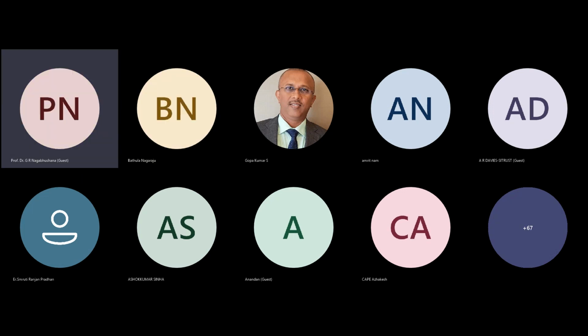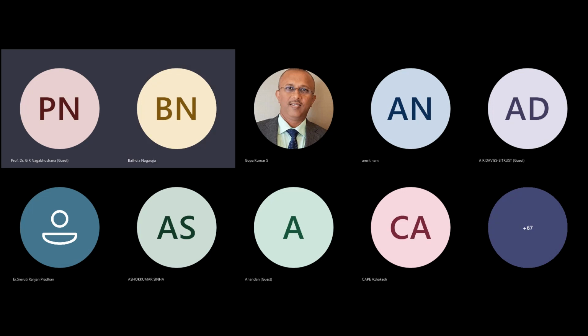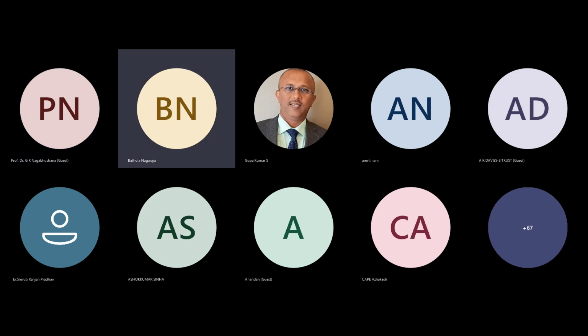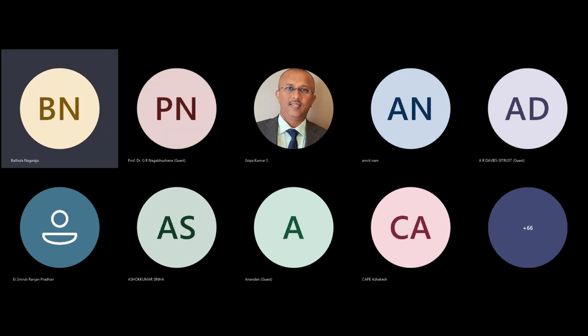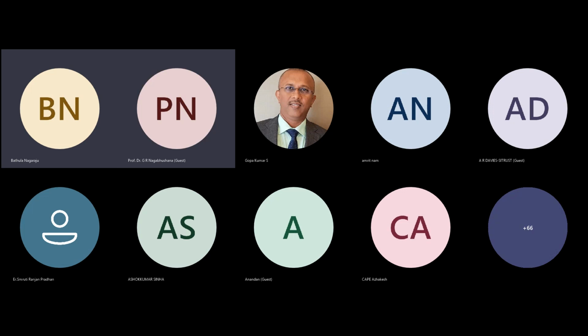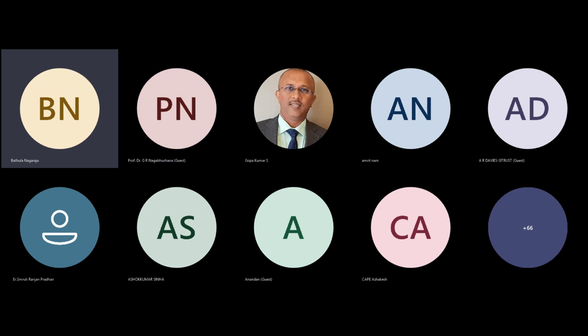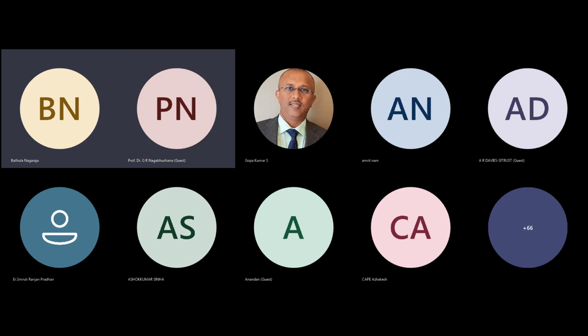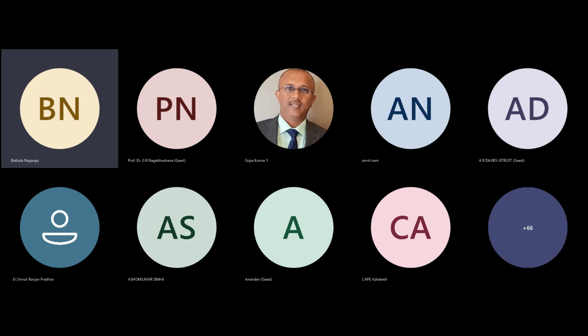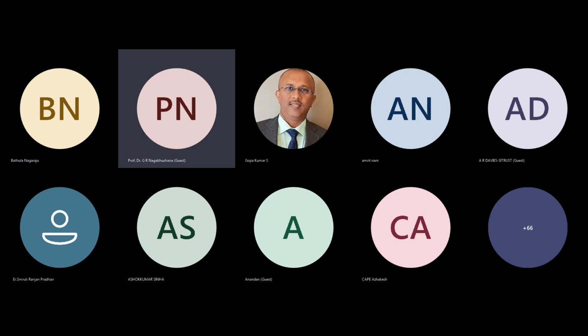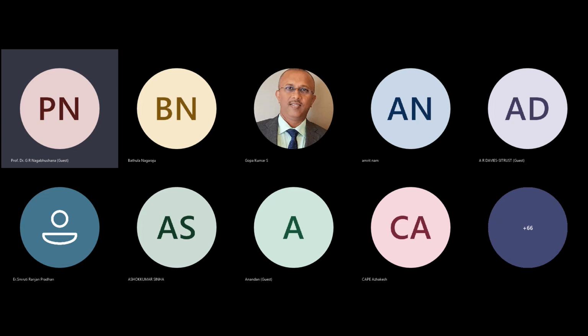The point of strike. What's the height of the tower, the down aerial terminal? Actually, it is around a 45 meter structure, sir, where hydrogen is present. Its IBD, intra-barrier distance, is around 30 meters, sir. What could be the approximate point of strike? We can put 8 termination rods. I think it would need a person-to-person discussion.